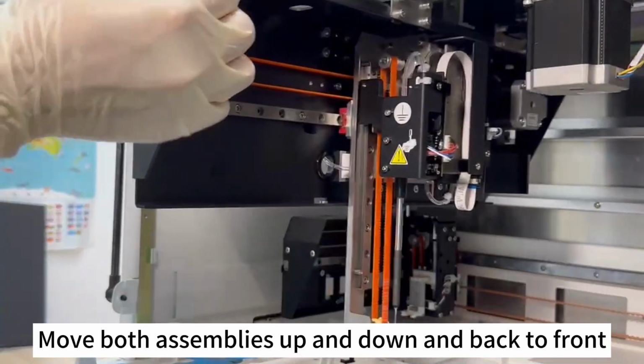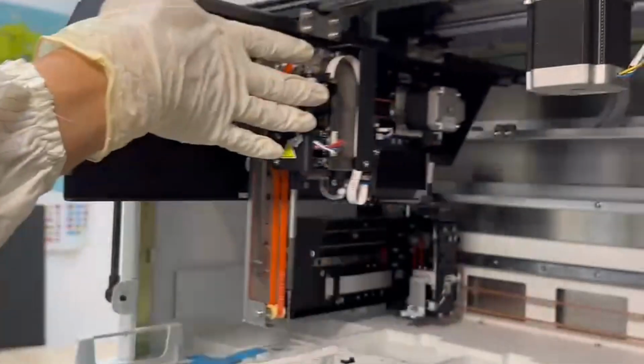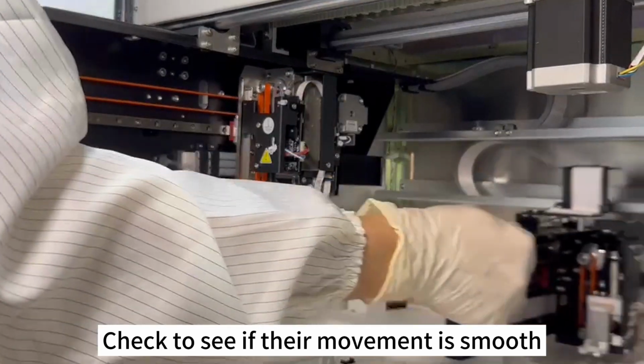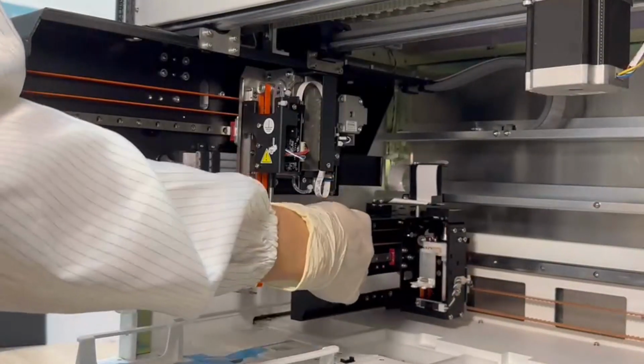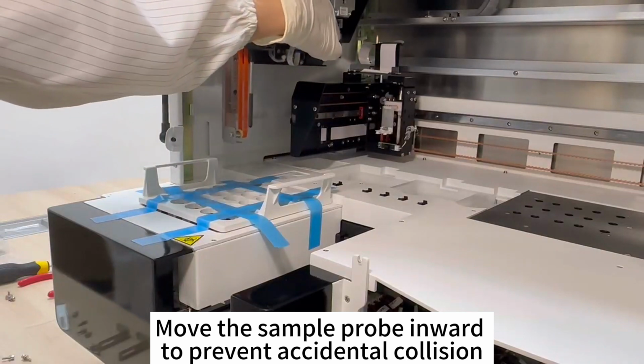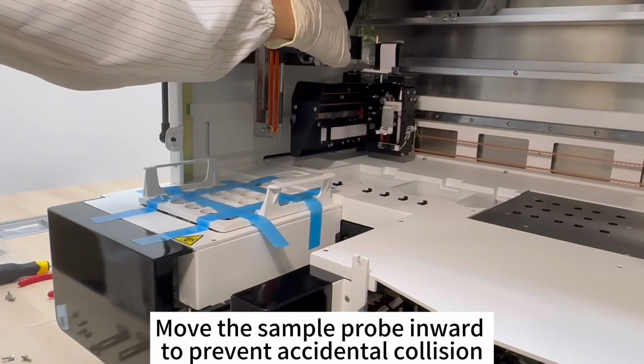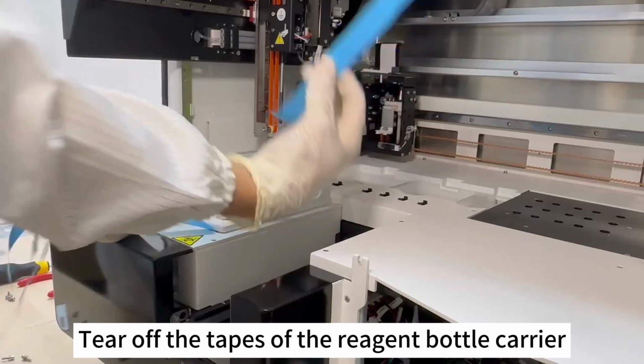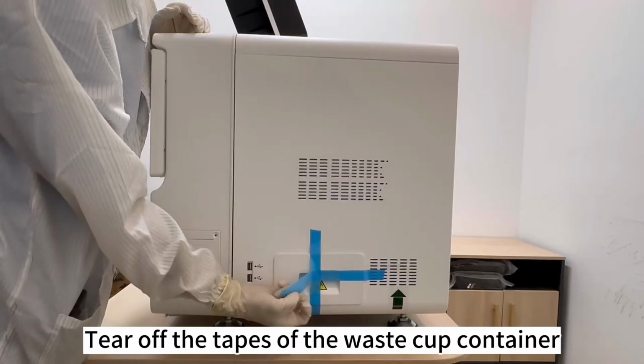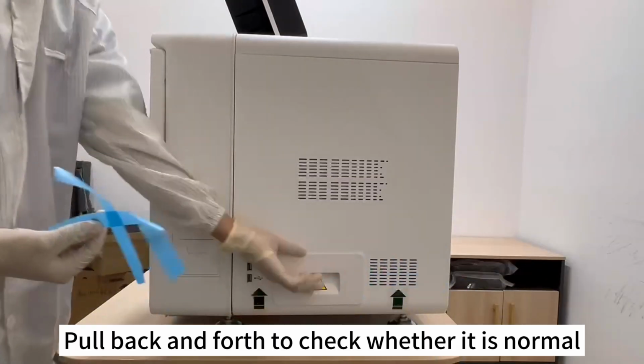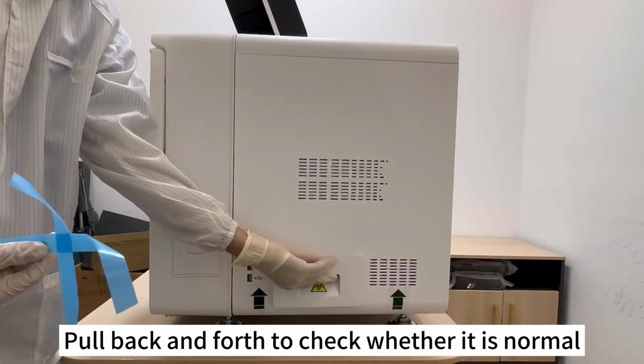Move both assemblies up and down and back to front. Check to see if their movement is smooth. Move the sample probe inward to prevent accidental collision. Tear off the tapes of the reagent bottle carrier. Tear off the tapes of the waste cup container. Pull back and forth to check whether it is normal.